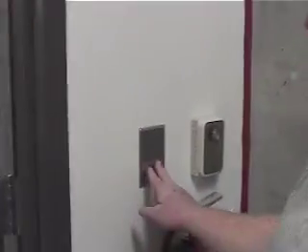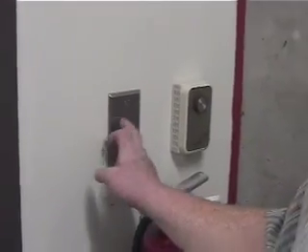So when the air handler shuts down or whatnot, it does have a fan coil unit that can turn the fan on and blow chilled air through the room to circulate the space. We do have an alarm in these 12 critical areas. We do have a flat plate sensor, which is actually a temperature sensor that does respond back to the system that will alarm you if it gets too hot or too cold. And we do have the ability to enable the air handler to turn on to provide cooling if it got too hot.